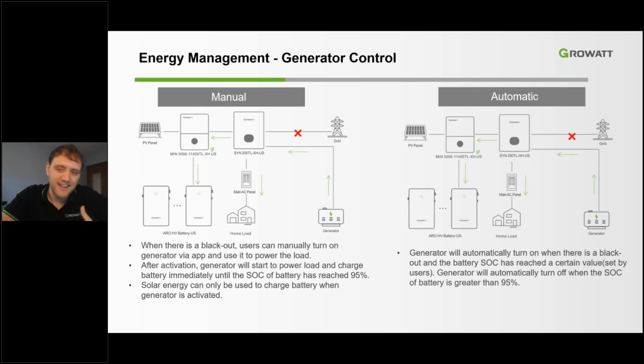The generator should be sized so that it can produce twice the energy as the inverter, up to 20 kilowatts, and that is the maximum limit for the generator capacity. And this allows for the generator to power the customer loads while simultaneously charging the battery. The battery is charged by the generator until the state of charge of the battery has reached 95%, then switches to the battery to power the customer's loads.